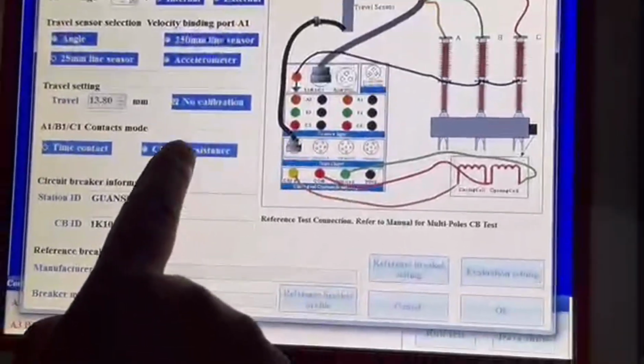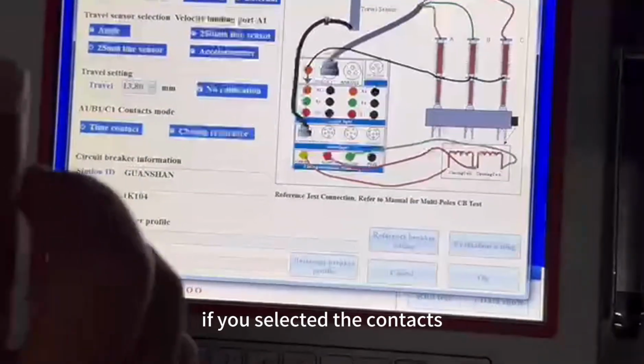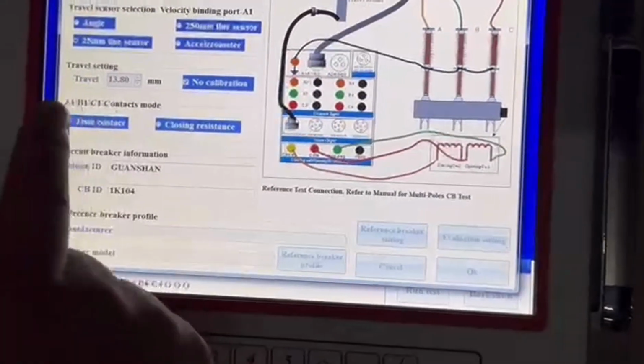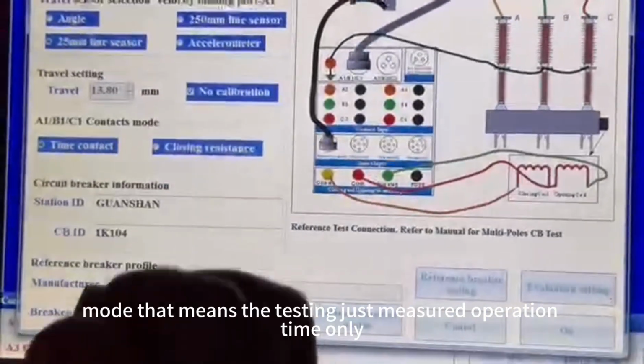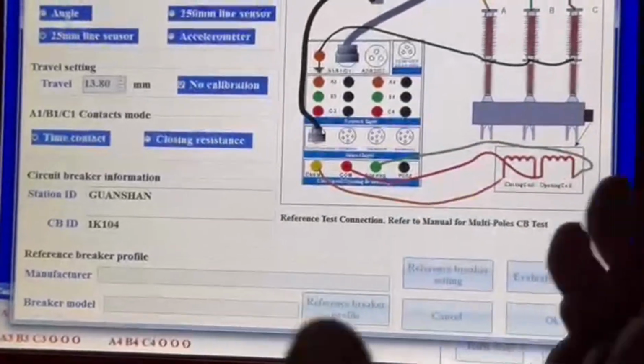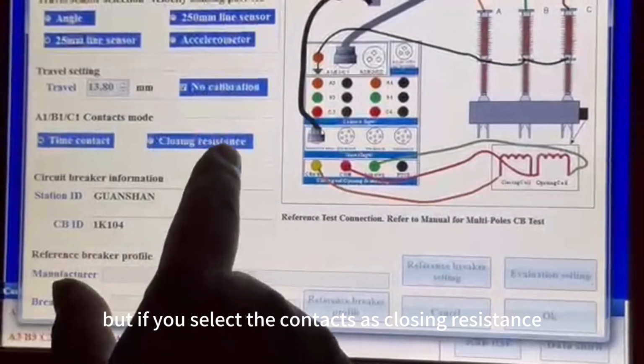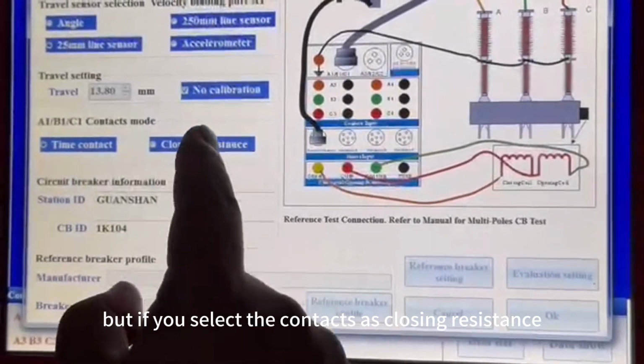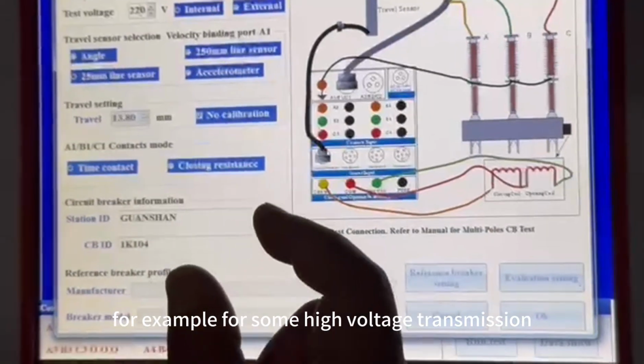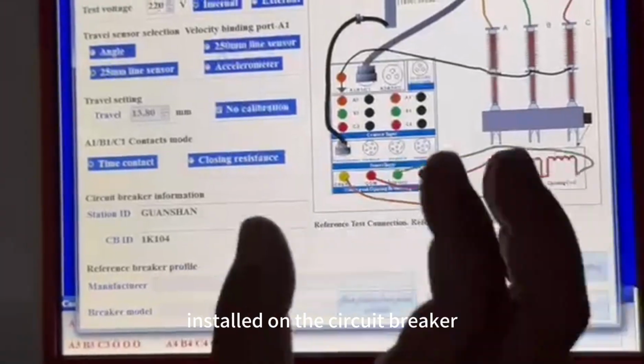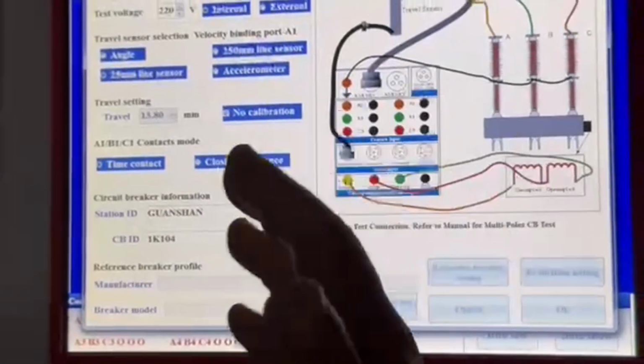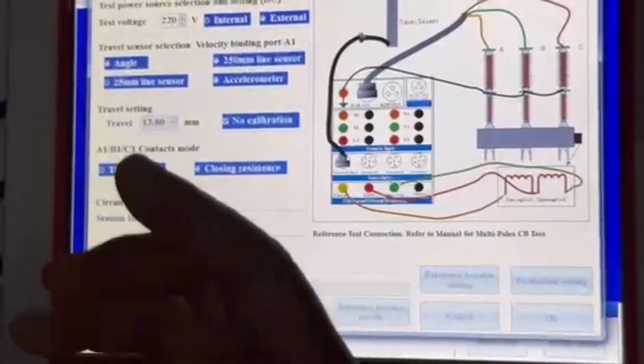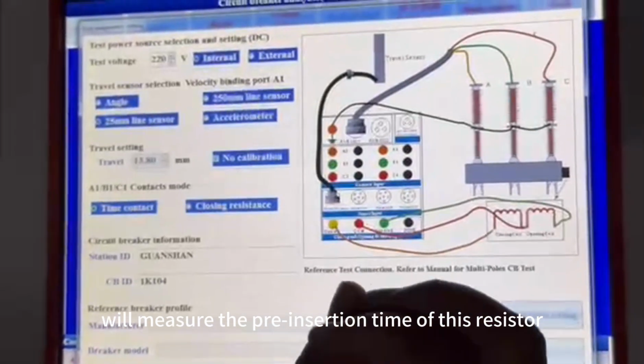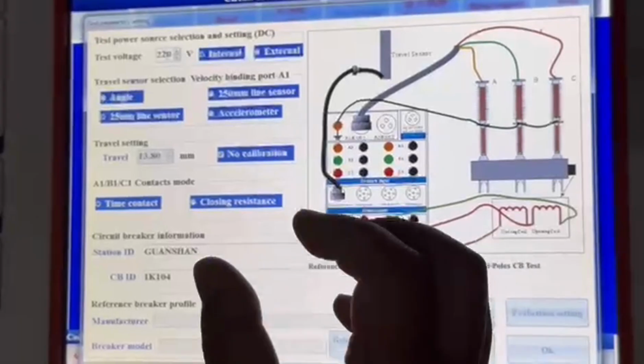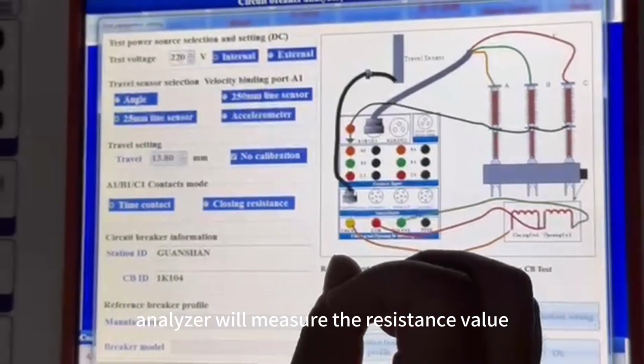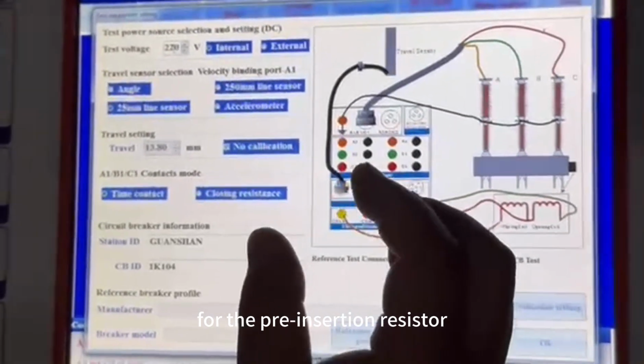The contact mode. If you select the contact mode as time mode, that means the test just measures the operation time only. But if you select the contact mode as closing resistance, for example, for some high voltage transmission circuit breakers, there is a pre-insertion resistor installed on the circuit breaker. In this mode, the circuit breaker analyzer will measure the pre-insertion time of this resistor, and the analyzer will also measure the resistance value of the pre-insertion resistor.